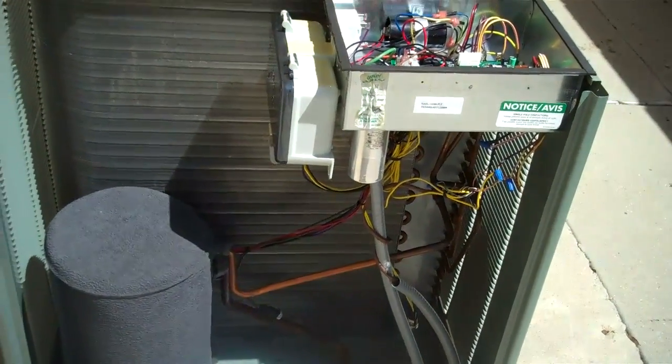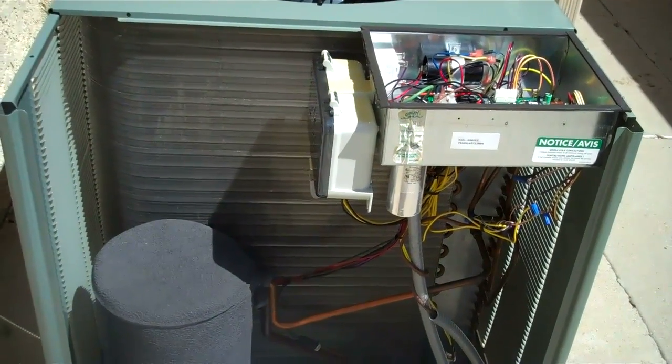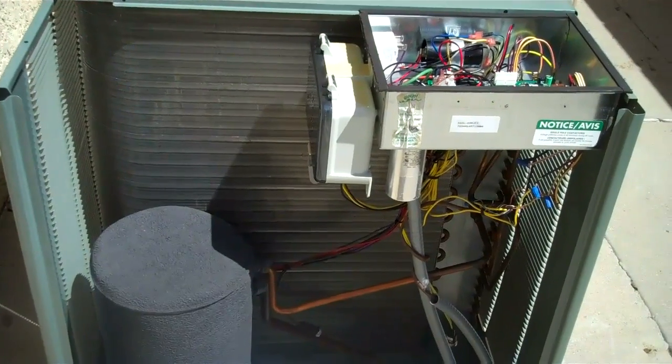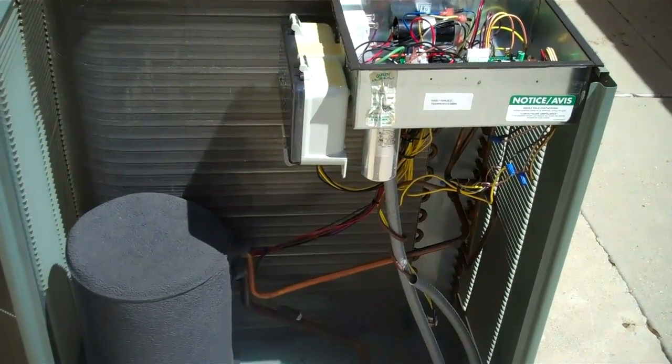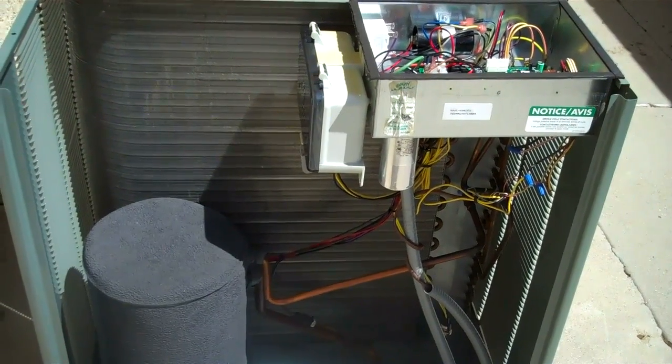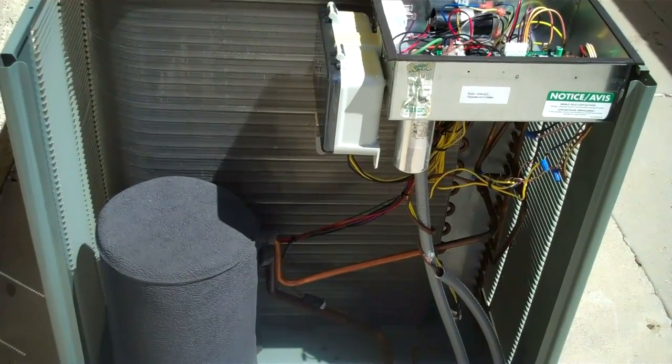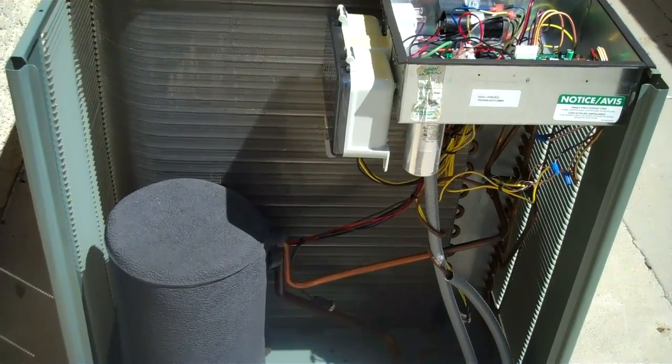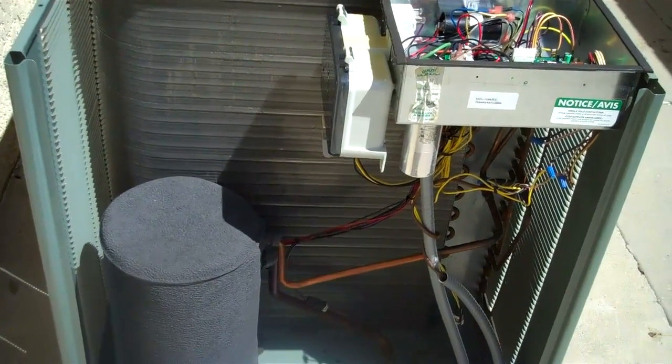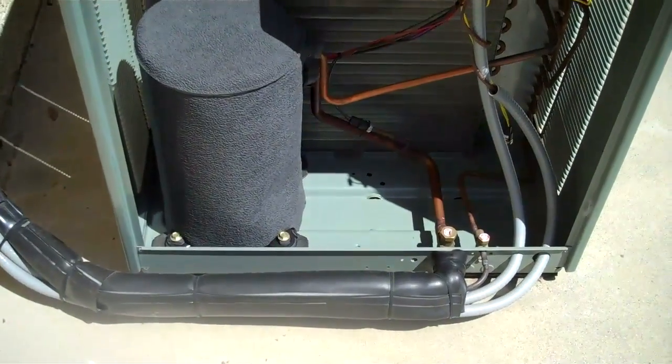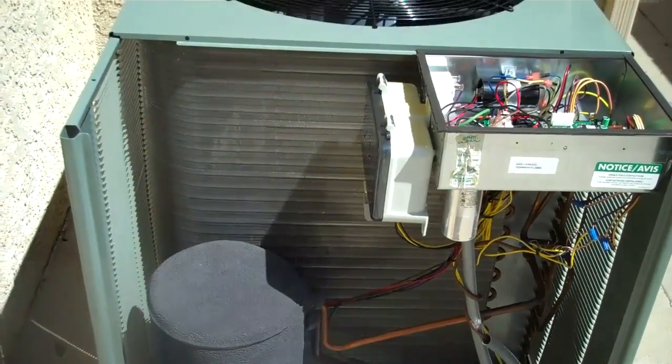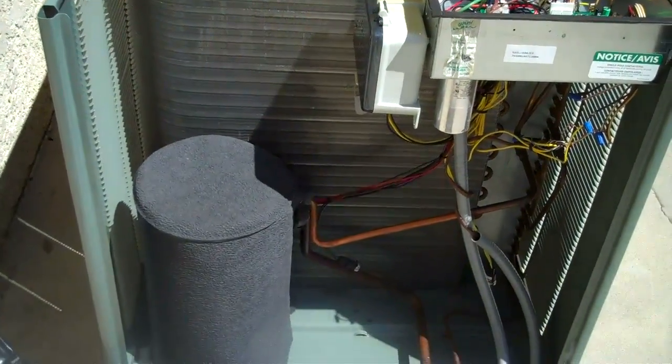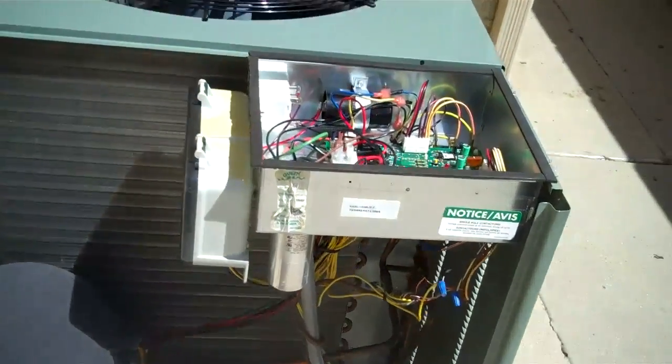Let's say that you're going to move this condenser, you have to pump it down, this is how you pump it down, you just, I put 24 to those, because it doesn't have a contactor, and you can pump it down this way. You know, you can bypass your highs and lows, or your low. So, you can pump it down this way. So, another little trick you can do.